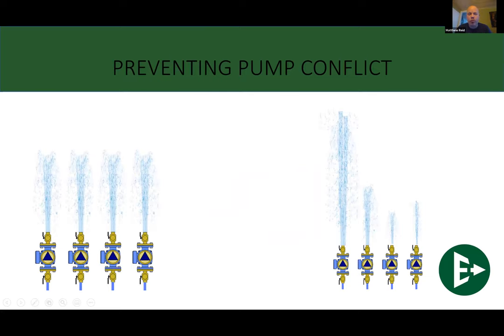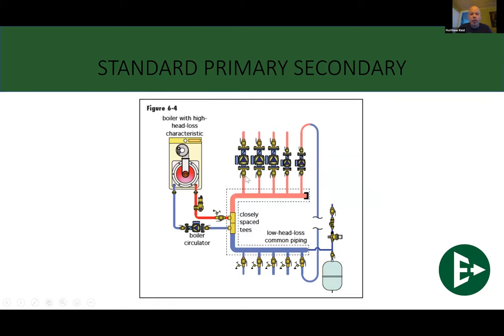If you start whipping it through too fast, you can erode the inside of the heat exchanger. Or likewise, you don't want a system pump pushing against another system pump. So the way that we design systems is going to be pertinent to make sure that we don't have conflict between our piping systems. Now, this one is preventing conflict between the boiler and the system. And that is done through a set of closely spaced tees. Closely spaced tees are, currently in North America, one of the jewels of the system here.